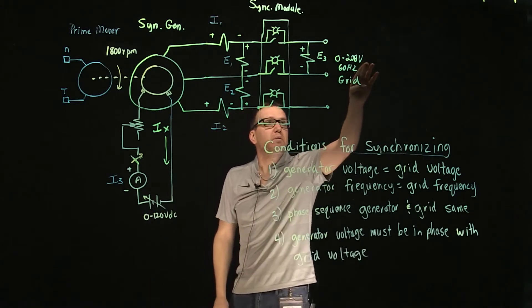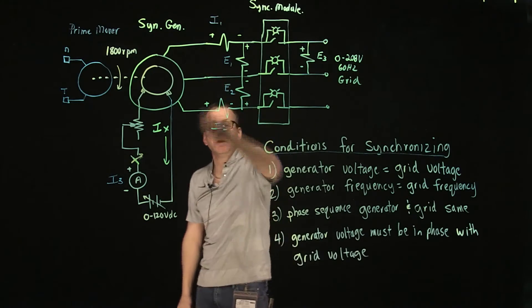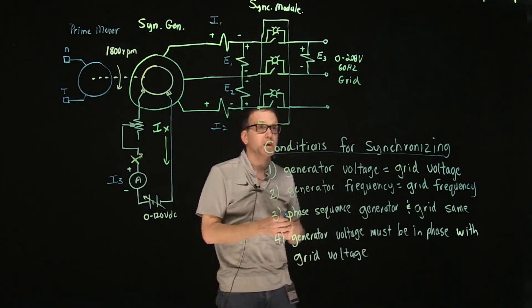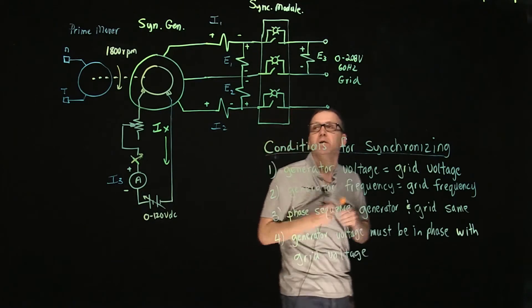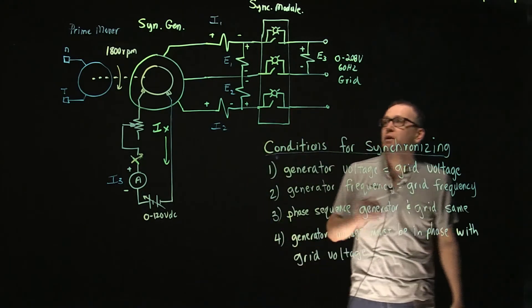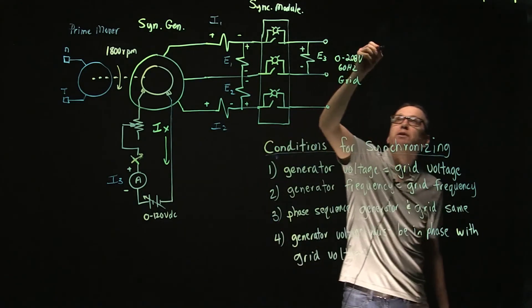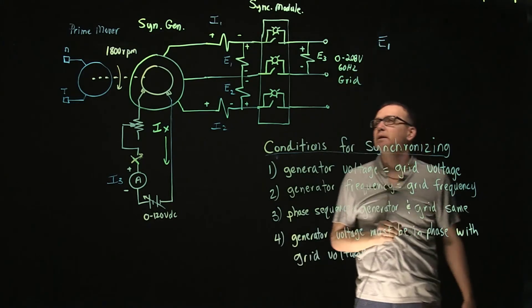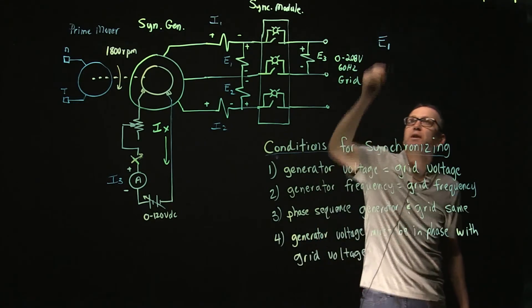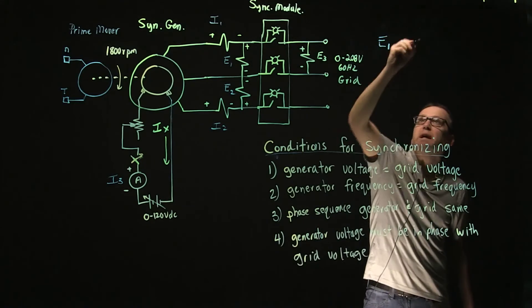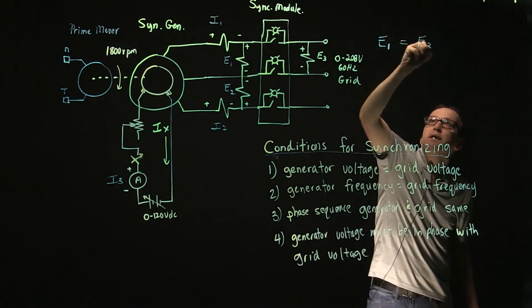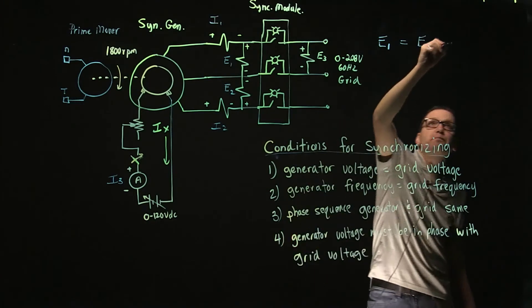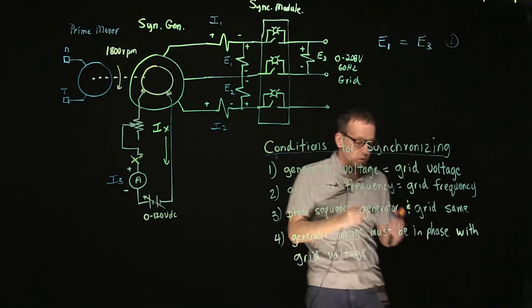The grid voltage is 208 volts. We want to increase the generator voltage until we get 208 volts — that will be condition number one. The meter we are using to observe the generator voltage is E1. We want to make E1 equal to E3, which is the grid voltage. This gives us condition number one.